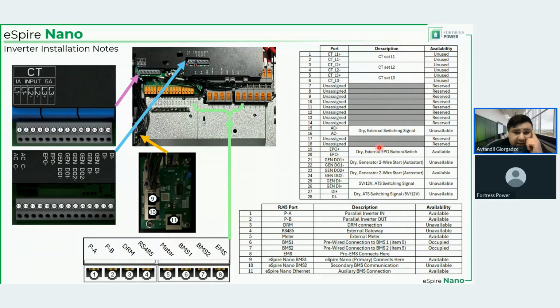And also the second one I want to direct your attention to is Gen DO2 plus and Gen DO2 minus, so digital output 2. This is what is used for auto start of the generator. CTs, you're not going to use them because we're going to use the meter. It's never allowed in our configuration to have the CTs Gauss coils directly connecting to the CT ports here, especially considering that these are for only up to 300 amps.